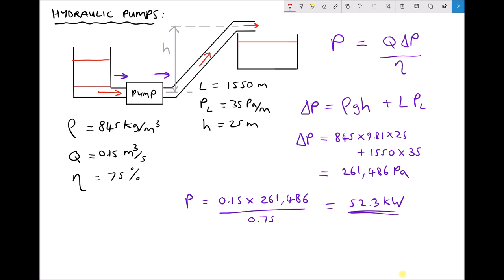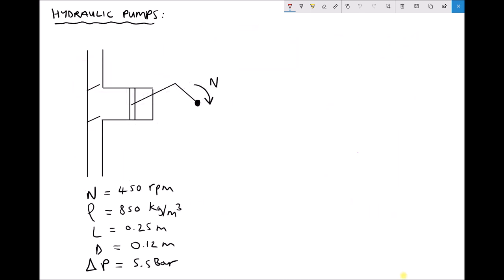Now that we understand the general function of the pump, let's look at a specific type known as a reciprocating pump. With a reciprocating pump, we can calculate the volume flow rate based on various characteristics. We have a piston mounted on a crank, and as the crank rotates the piston retracts and extends. When the piston retracts, oil is drawn in through the lower pipe into the cylinder, causing the top valve to close and the bottom valve to open. On the forward stroke, the lower valve closes, the upper valve opens, and the piston pushes fluid out through the discharge pipe.